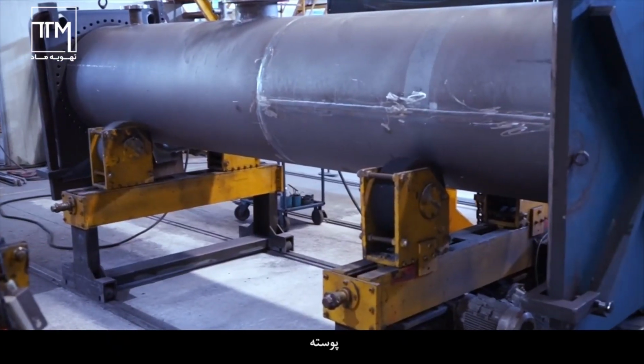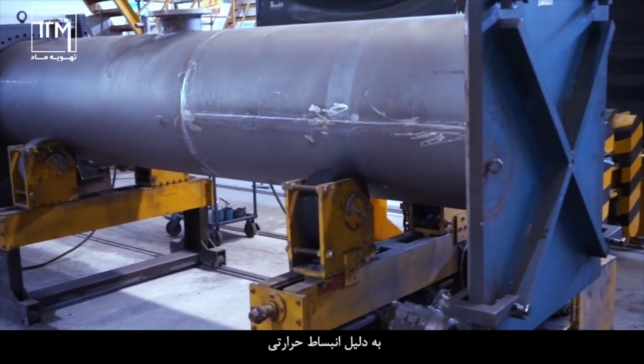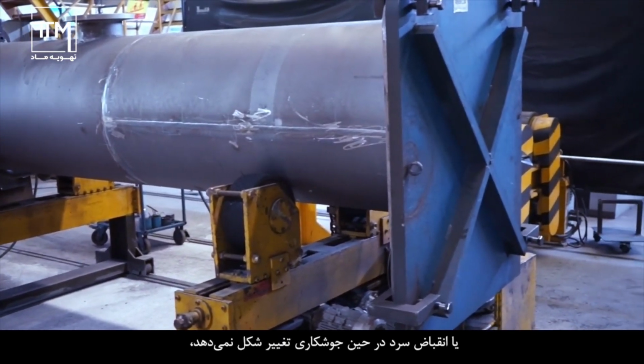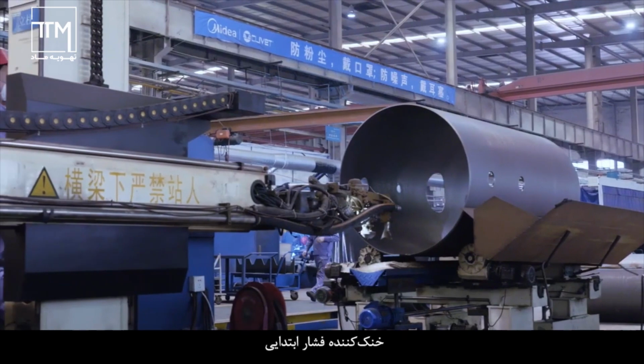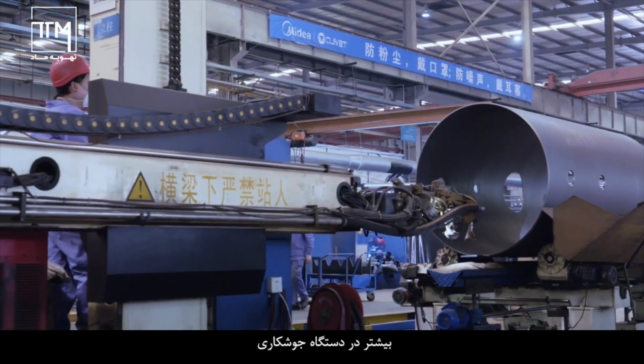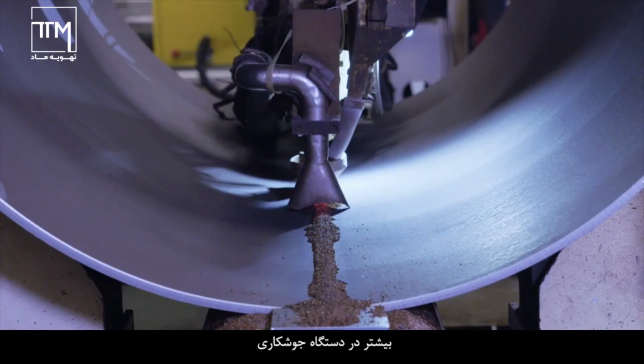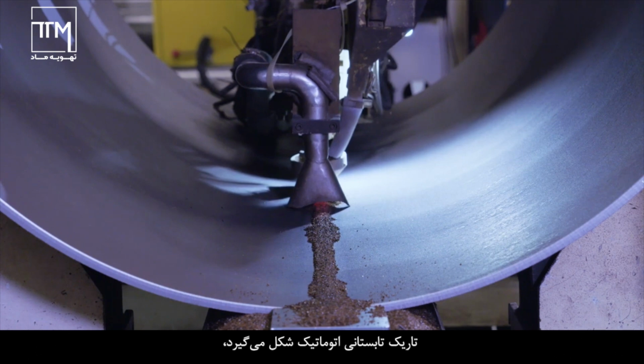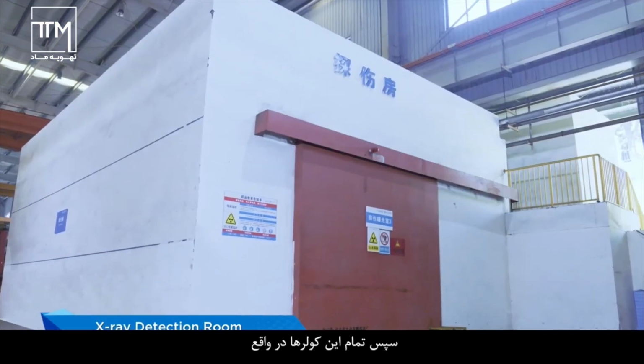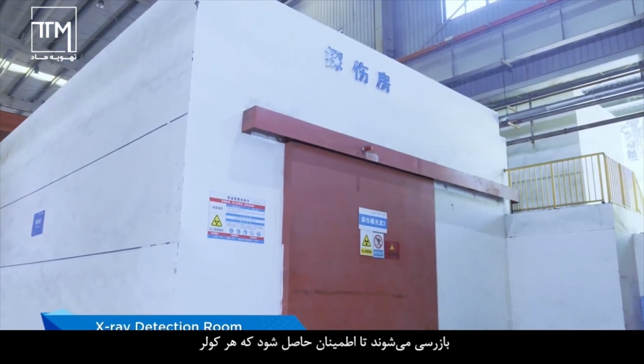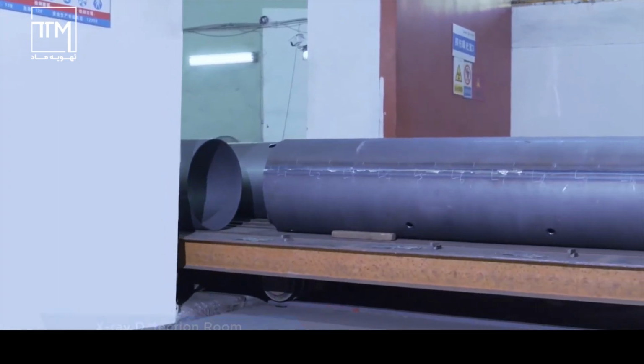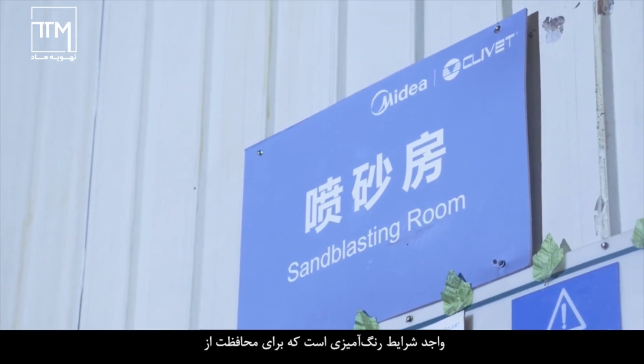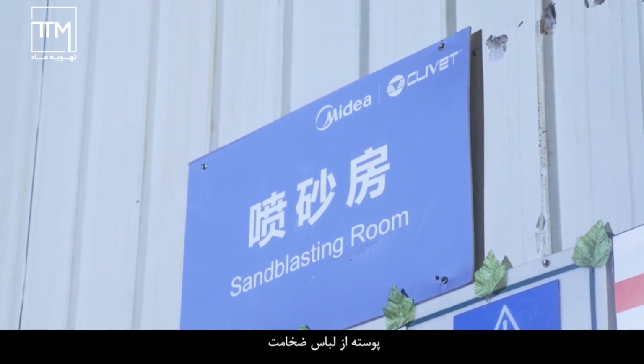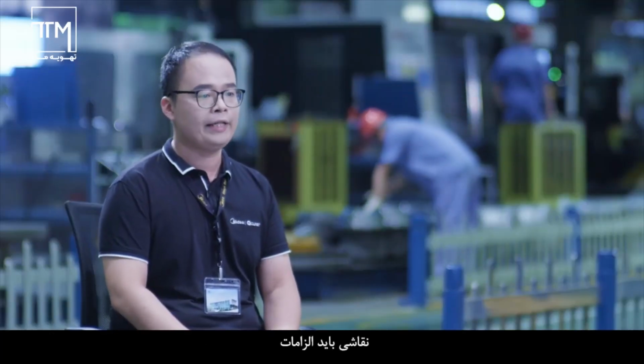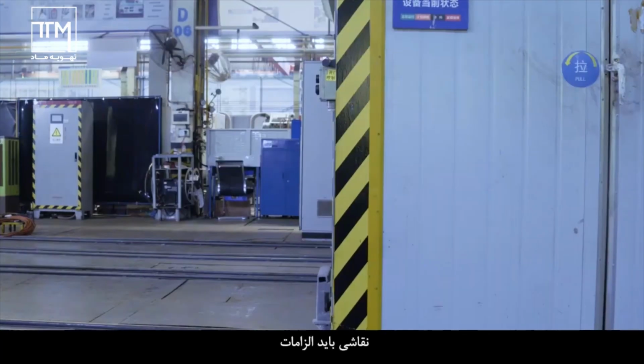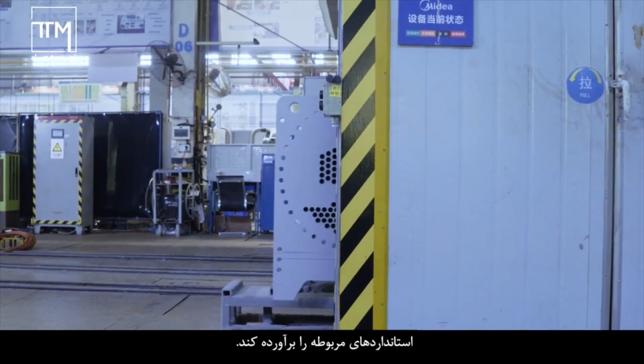The fixed support ensures that the shell will not deform due to thermal expansion or cold contraction during welding. The rudiment of the pressure cooler will be further formed in the automatic submerged arc welding machine. Then all these coolers will be X-ray inspected to make sure each cooler will be qualified. Painting is necessary to protect the shell from corrosion. The thickness of the painting must meet the requirements of the related standards.